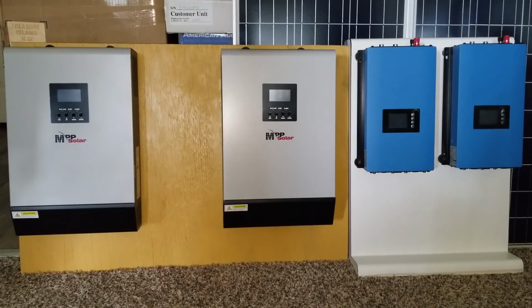It makes sure it reaches exactly the demand so you cannot put power back to the grid, and it monitors the other line too. The clamps go on each leg coming from outside, from the grid, into your box, and monitor both of them for the 240 configuration of your house, which is 120/120.